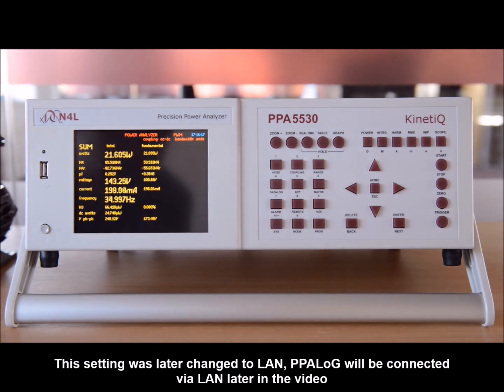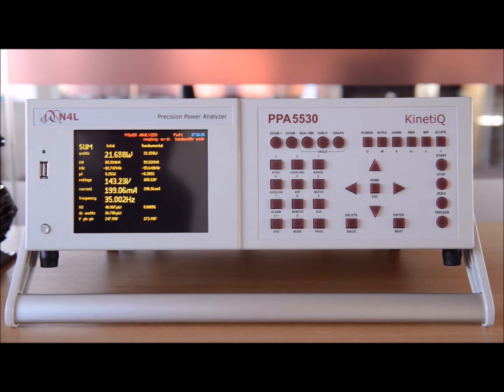Of course, this is off-load, so there's not going to be fantastic efficiency, as you may have guessed from the 27 watts in to the 21 watts out, but it's going to be a very accurate efficiency measurement nevertheless, using two different models within the range of power analyzers. And I'll show you how that's no problem interfacing the two together. We don't have to have two PPA5500s connected together, for example. We can mix the models. So let's have a look.